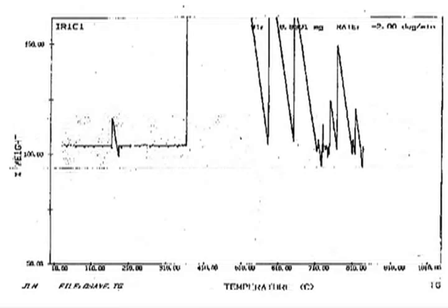And you know, that does happen. So we said, we got to check this. But just out of curiosity, once it settled down here, this is actually the same place it ended before. See, we started right there to cool, and actually right there is stable. Other than that one hiccup, which lasted about 4 or 5 minutes, it's basically stable. I said, well, tell you what, don't take it out. Let's just heat it again.